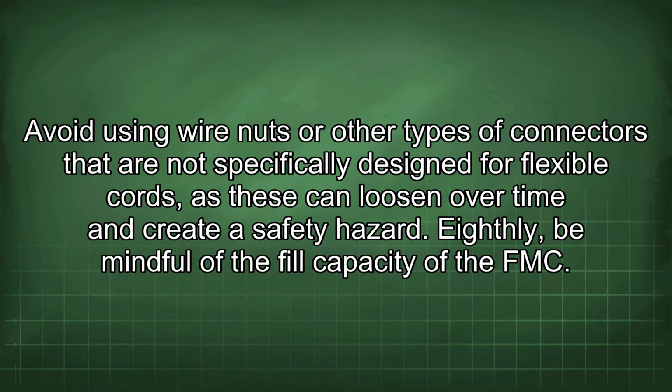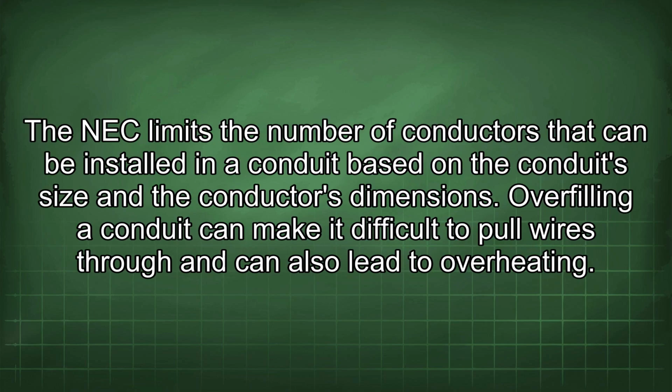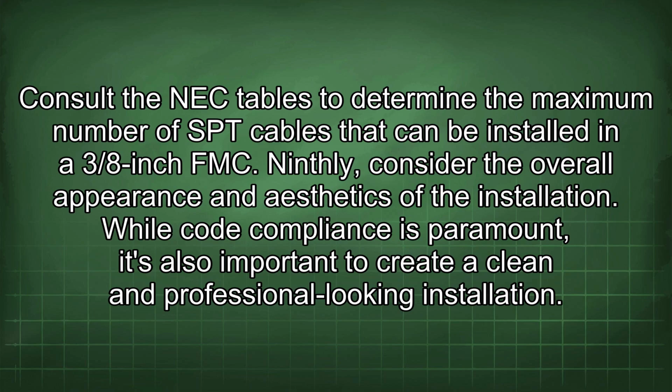Eighthly, be mindful of the fill capacity of the FMC. The NEC limits the number of conductors that can be installed in a conduit based on the conduit size and the conductor's dimensions. Overfilling a conduit can make it difficult to pull wires through and can also lead to overheating. Consult the NEC tables to determine the maximum number of SPT cables that can be installed in a 3/8-inch FMC.